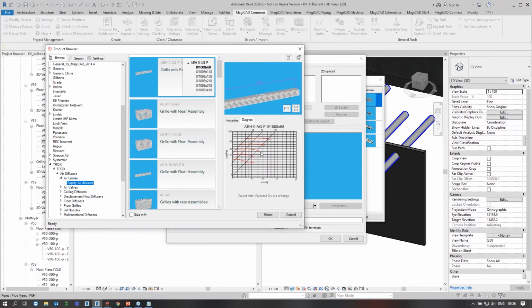We can see, yeah. And in this, it was one question if you use BIM software, I thought it was in the poll, BIM, Building Information Modeling. For a ventilation guy, at least an engineer, the information, the I in BIM, is the pressure drop diagrams. And the red curves are, of course, how much sound this product is generating. For a ventilation engineer, of course, we need to do some calculations. Without pressure drop diagrams, you can't do balancing, because when we are doing the balancing, we are going to see an operation point.